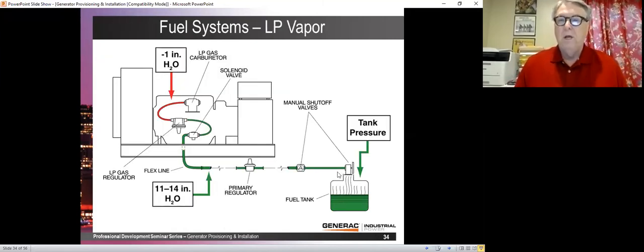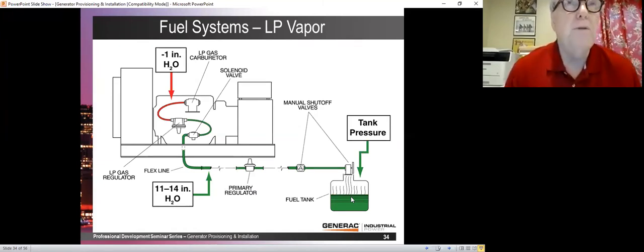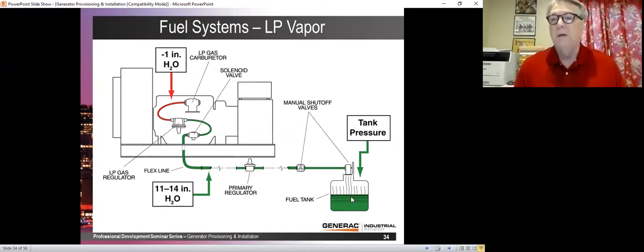Here's LP vapor. The problem with LP vapor is the tank must be able to vaporize. We still want 10 feet to our generator between the primary regulator and the generator, 10-foot pipe length, not distance. And you've got to be able to vaporize. Now, as it vaporizes, the tanks get colder, and that's the reason we use propane rather than butane, is it vaporizes much better.